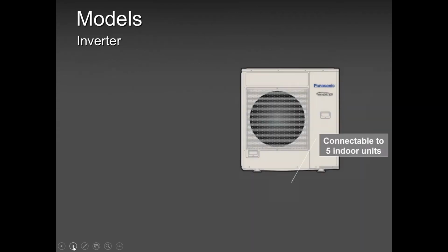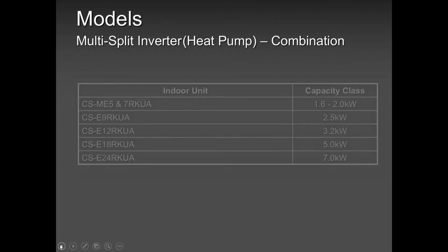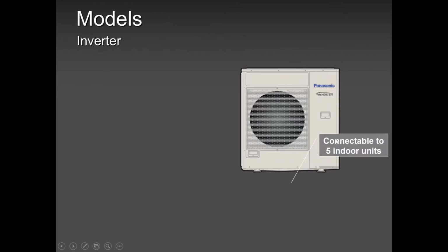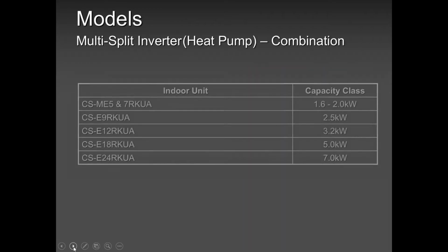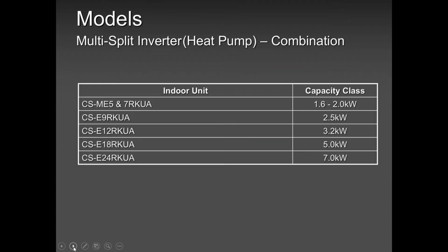And this compressor comes with a crankcase heater. All our multi-zone unit compressors come with a crankcase heater to keep the compressor warm. So don't worry if the unit is on, there is no issue. Do you see here what it says? Connectable 5 indoor units. This unit can connect up to 5 indoor units. However, a minimum of 2 indoor units is important.